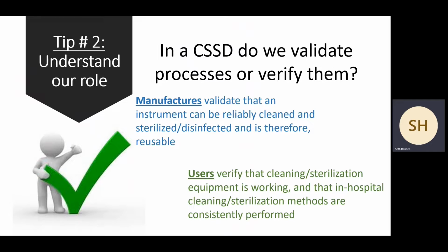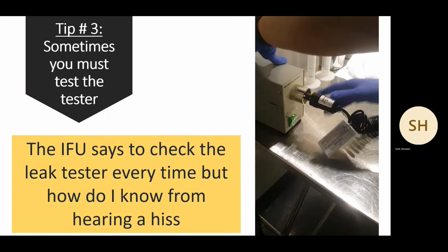And endoscopes and shavers are a perfect example of that, where the FDA has come out and said, even if you follow the manufacturer's instructions specifically, you need to then come behind and do some checking to make sure that that process actually works. So that's an even higher form of validating the fact that that process did actually occur as the manufacturer validated it too.